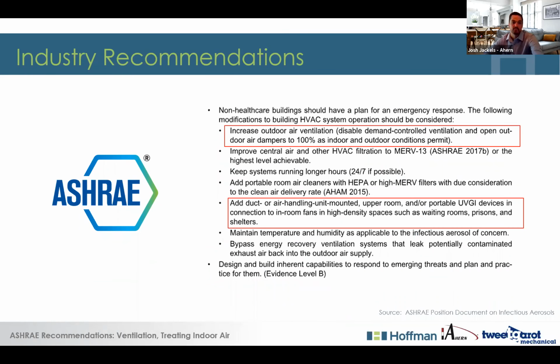The next recommendations I will review are provided by ASHRAE, which is a noted HVAC industry leader in codes and recommendations. ASHRAE's COVID-19 recommendations are very consistent with what CDC has suggested: increase outdoor air ventilation, add duct or air handling mounted upper room or portable UVGI devices, as well as improve HVAC filtration with a noted MERV rating of 13. I again boxed in the discussion points of outdoor air ventilation as well as UVGI, as we will expand upon these topics further on in this presentation.